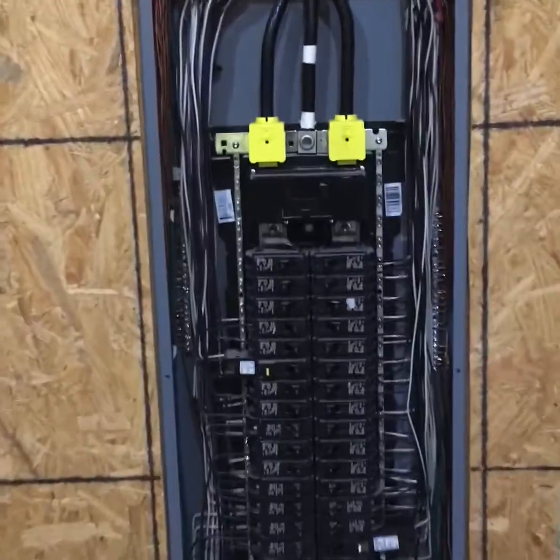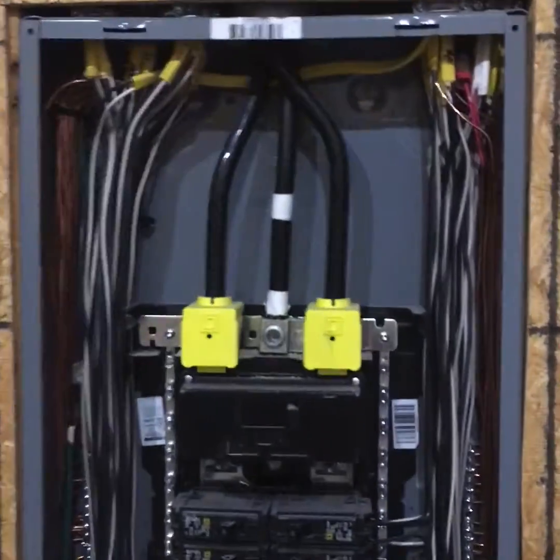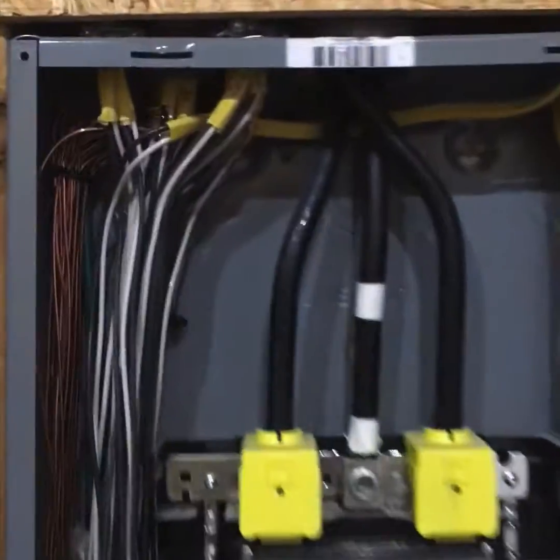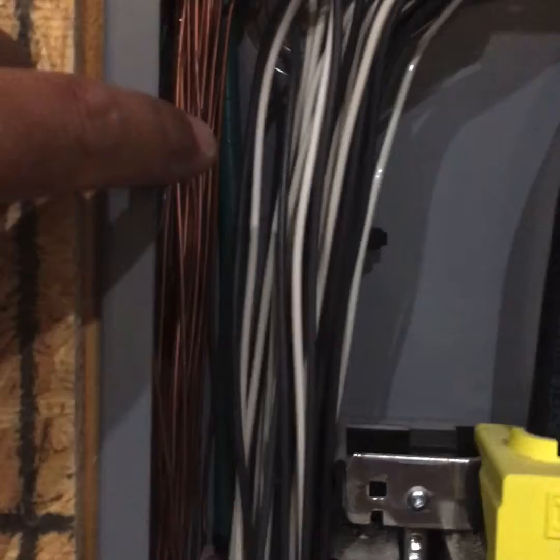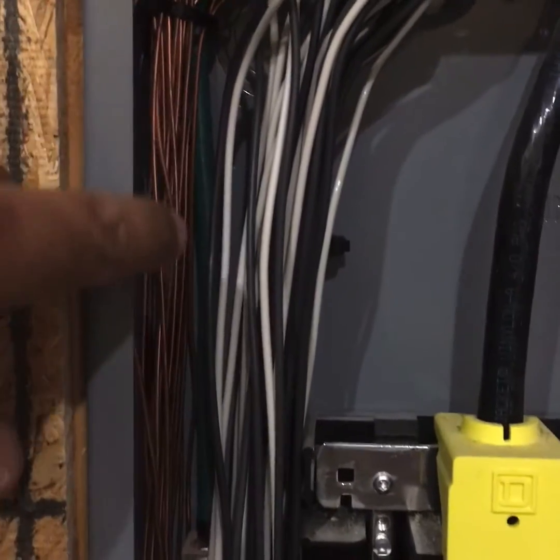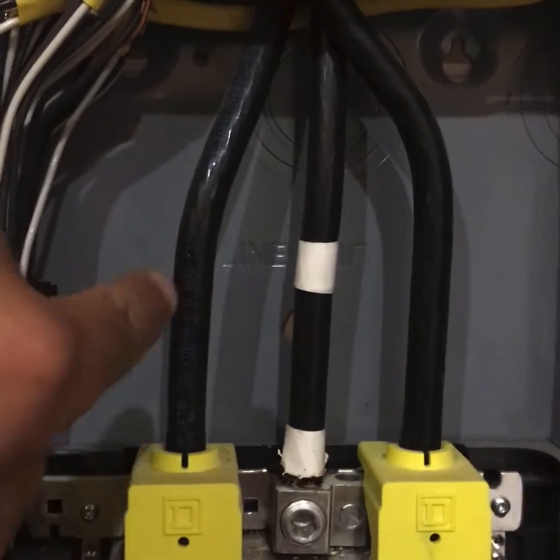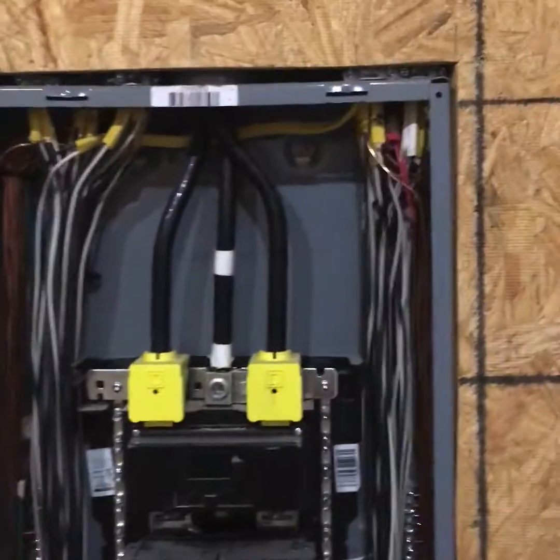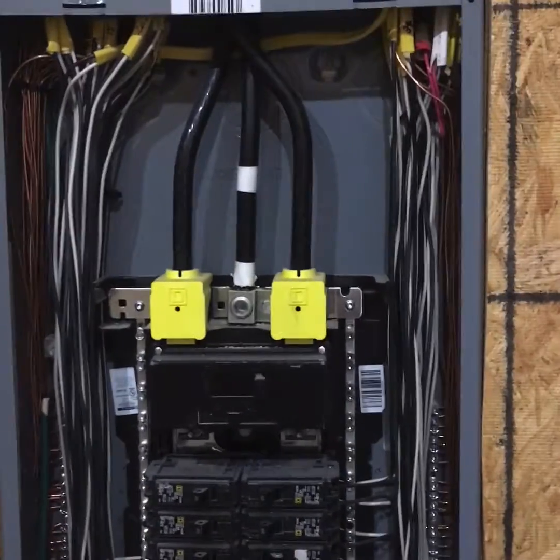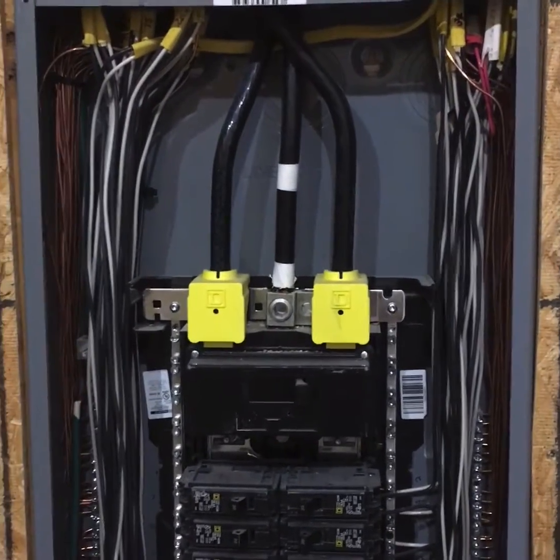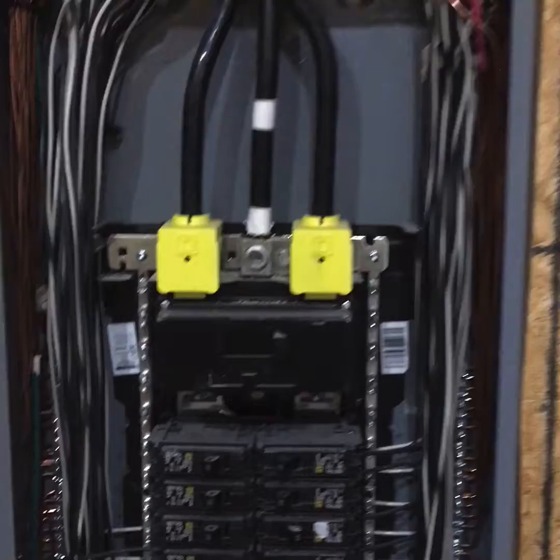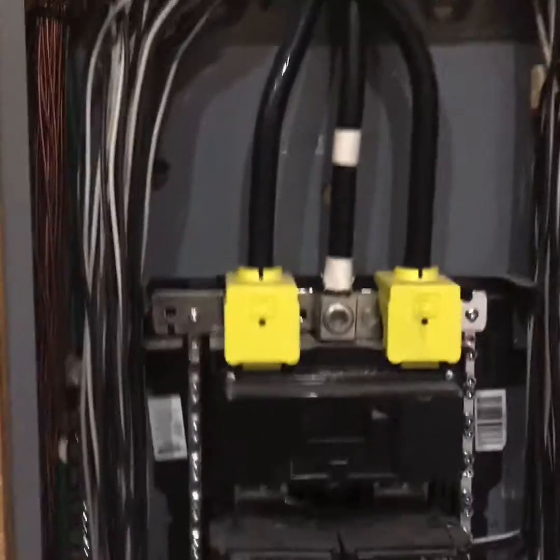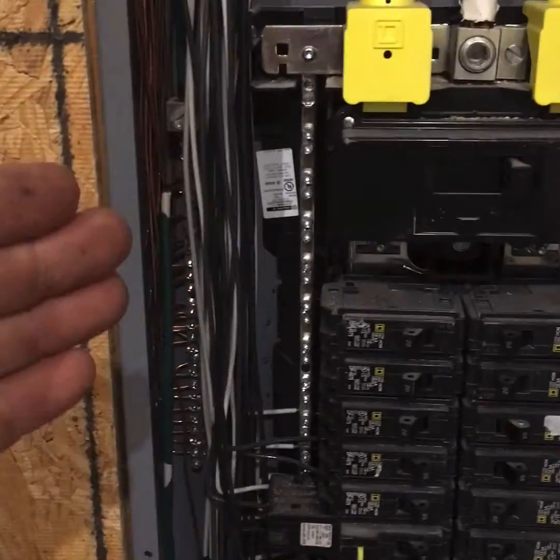So this panel here I installed, this is a sub panel. What makes it a sub panel is we have a separate ground wire here, a separate ground conductor. So we have 1, 2, 3, 4 conductors: line 1, line 2, neutral, and then ground, and they go outside to a primary disconnect where the ground and the neutral are connected back together, and there's also a ground rod. So on this sub panel, we're going to separate our neutrals and our grounds.